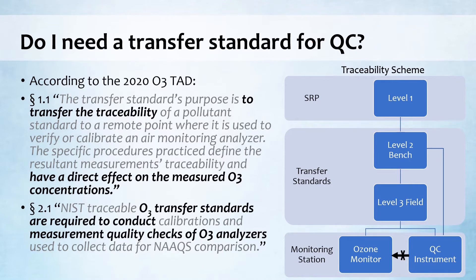However, in Section 2.1 of the 2020 Ozone TAD, it explicitly states that ozone transfer standards are required to conduct measurement quality checks of ozone analyzers. Here's the general traceability scheme of our district. We don't use a level 2 bench, and we don't use the QC instrument to adjust the ozone monitor. So we were treating the QC instrument similar to an ozone analyzer.